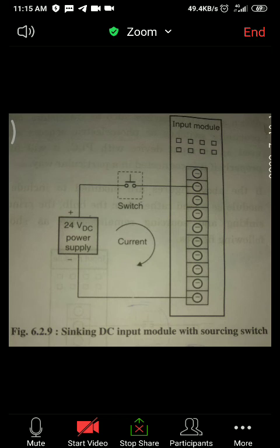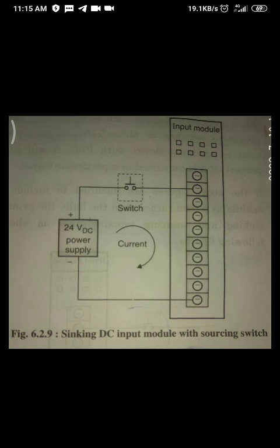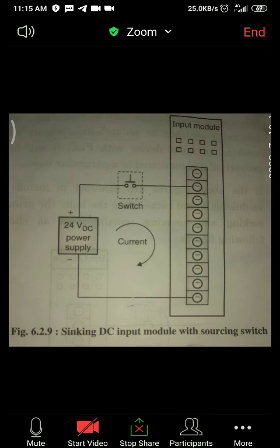Means what? If you are connecting any transistor in a circuit which is acting as an input terminal, then it should be the sourcing device. Instead of the switch, there will be a transistor, but that transistor should be in the sourcing mode. Okay. But if you are using a sensor, then what? A sensor cannot act as a source of energy. So you have to connect it in the sinking manner.